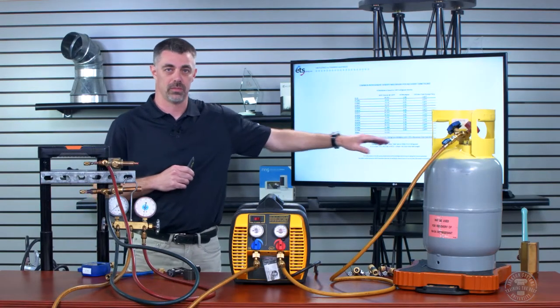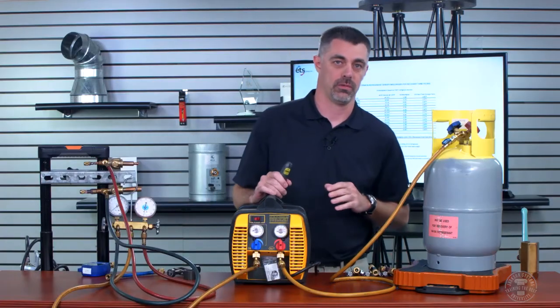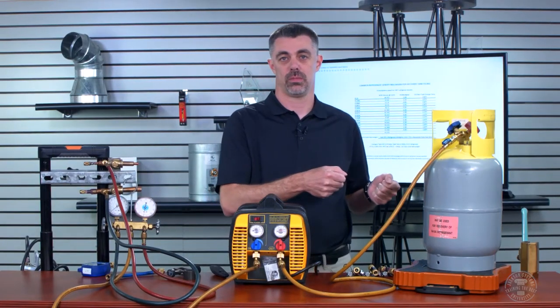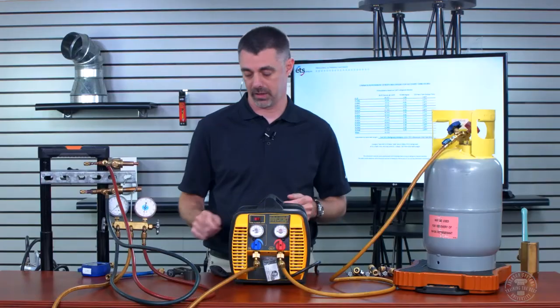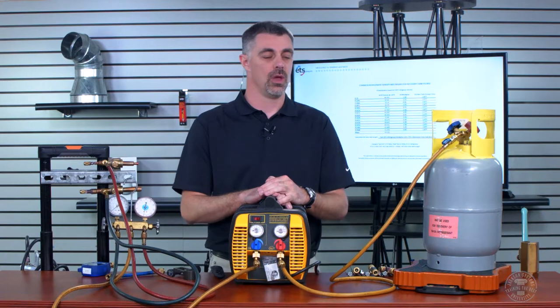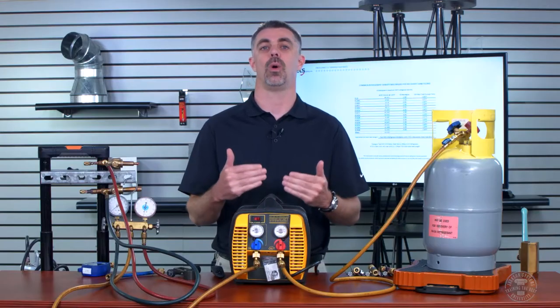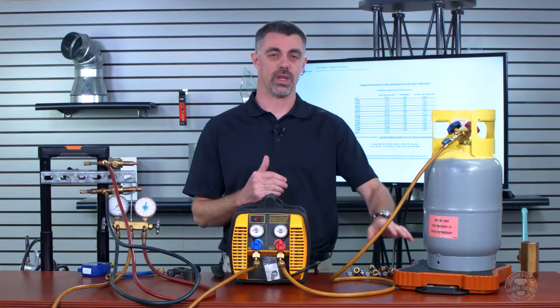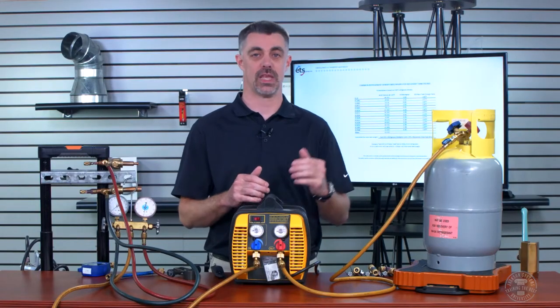Anytime we're filling a tank, we need a scale under it. You should never leave the scale behind and weigh the tank only at the truck, because you don't know how much refrigerant is actually in the system until you pull it all out. We need the scale under that tank at all times, watching the tank weight to make sure we're not overfilling.